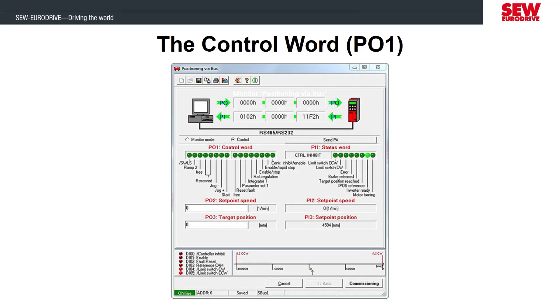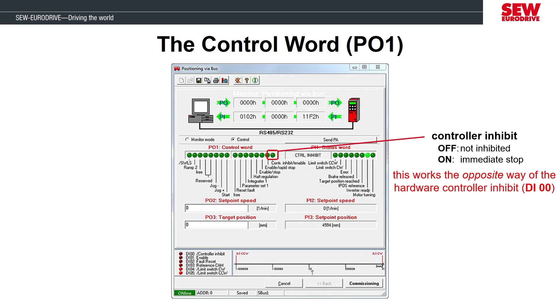Before we head to the software, let me explain the bits of the control word, since there are some differences from what we've done previously with the digital input switch box. Starting on the right, we have the controller inhibit bit. We will still have to set the hardwired DI00 inhibit like in the previous labs — you can see the status of those in the bottom left of the screen. But don't confuse this inhibit bit with DI00: it is not mandatory like the physical DI00 input. Its purpose is to put the Movi Drive into an inhibit state even if the physical DI00 input was still switched on. If you don't want inhibit from the control word, leave this bit off and just toggle the physical DI00 input.